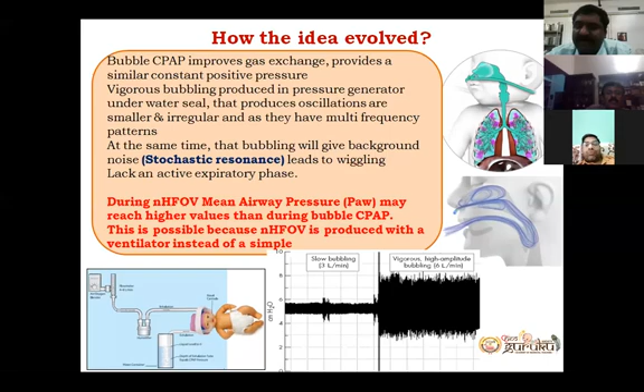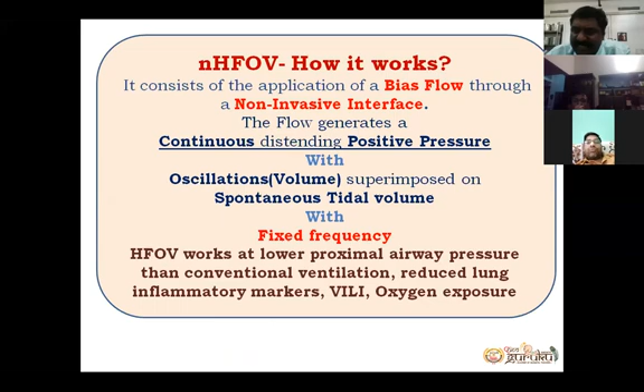Now, how it works, same thing I am telling you. Already, because of the bias flow, we have given the mean airway pressure. Because of the flow, it is generating oscillations, and we are imposing more tidal volume on the spontaneous breath. All those things. Please, my dear friends, see this. It's not flowing. Okay. See, what I want to keep is, one is membrane. This is how the bubble CPAP works. Non-invasive HFOV, it's a membrane. This is a piston. So this is a valve type. Please go through. Please, this is a very important slide.